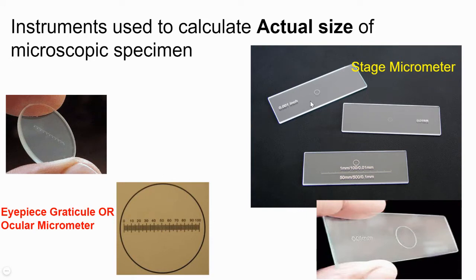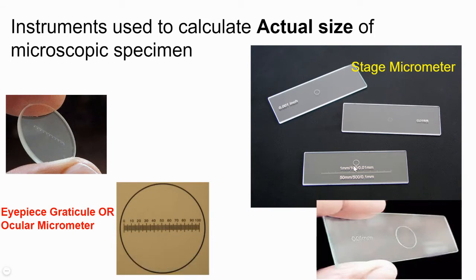permanently, scales have been printed or scratched onto the center of this slide. These scales are extremely small so you cannot see each division clearly. The slide itself gives information about the size of the scale — sometimes about 1 millimeter, sometimes 0.01 millimeter for the whole scale's length, and sometimes they also tell you the length of each division.